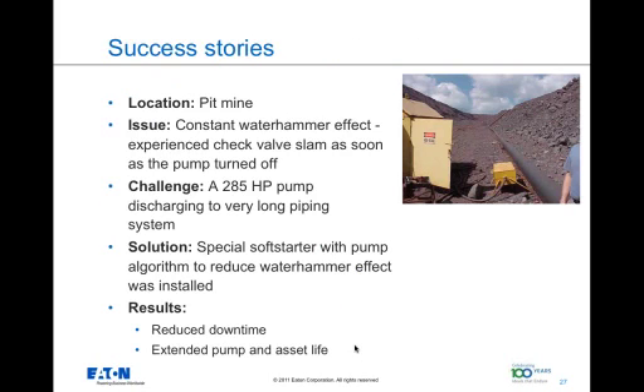and this customer was hesitant to use the soft starter at first, so we gave it to him at a discounted price just to make sure he understood the workings of the soft starter and felt comfortable about using it. Once he used it in this particular situation, where he had longer pipes pumping water into the pit mine, he drastically reduced the amount of water hammer coming into the system. And since then, this pit mine customer has across the board converted all his traditional reduced voltage mechanisms into soft starters. I think it was to the tune of about 100 soft starters or so that he has implemented in his mining facility.